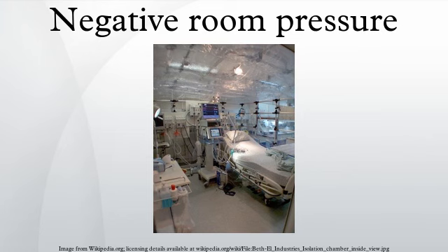Smoke test: a smoke test can help determine whether a room is under negative pressure. A tube containing smoke is held near the bottom of the negative pressure room door, about 2 inches in front of the door. The smoke tube is held parallel to the door, and a small amount of smoke is then generated by gently squeezing the bulb. Care is taken to release the smoke from the tube slowly to ensure the velocity of the smoke from the tube does not overpower the air velocity.